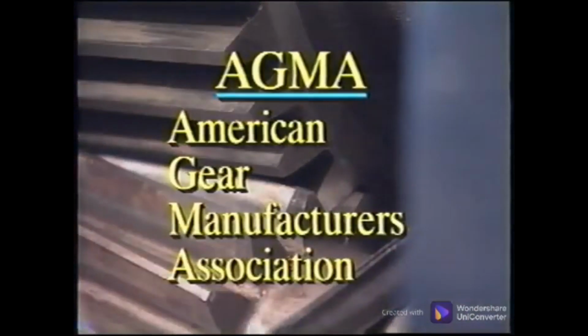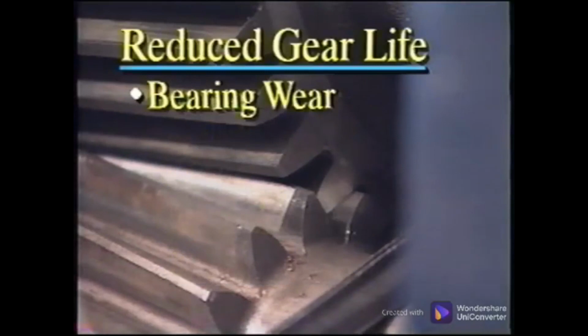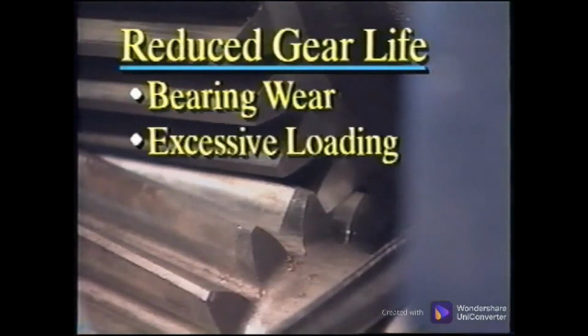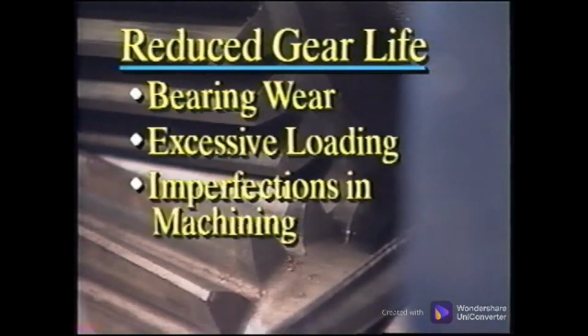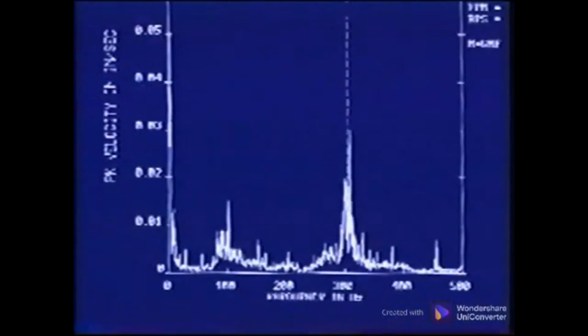A good set of gears with proper tolerances that conform to the standard set by AGMA, American Gear Manufacturers Association, should last 20 years or more. However, bearing wear, excessive loading, and imperfections in the machining and material of the parts can cause the in-service life to be reduced substantially. This spectrum is from the drive side of a paper machine.